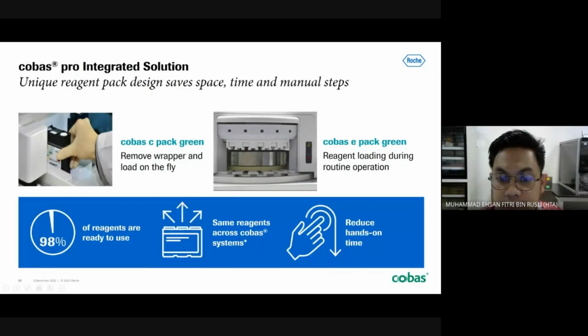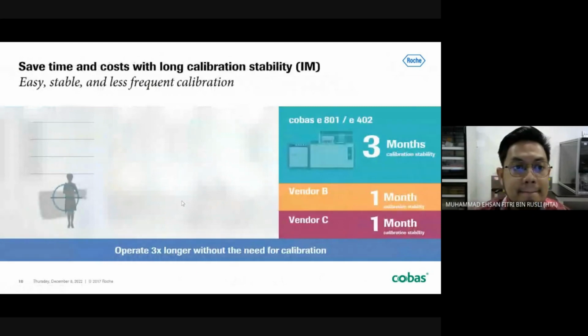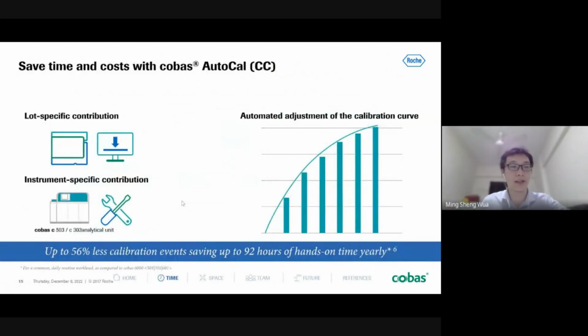Okay. So auto calibration, it is like this. Currently for analyzers, usually if you have a new lot, you have to do manual calibration, right? With AutoCal, if you receive a new lot, you don't need to do the manual calibration. What you need to do is go to the instrument and press download. It will automatically make the calibration curve for you. So this is what it means with auto calibration.